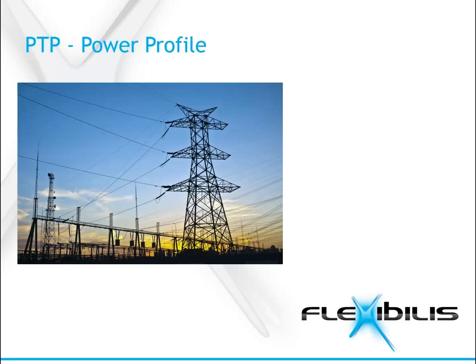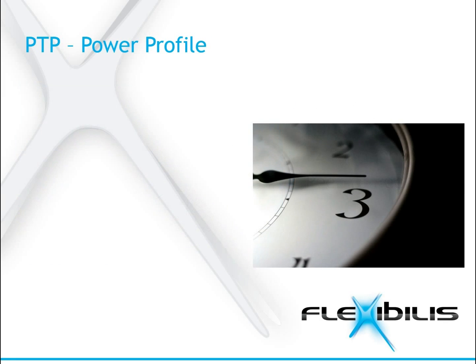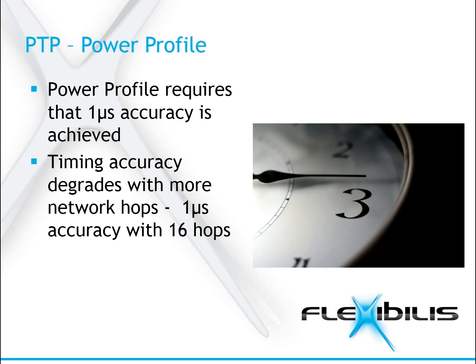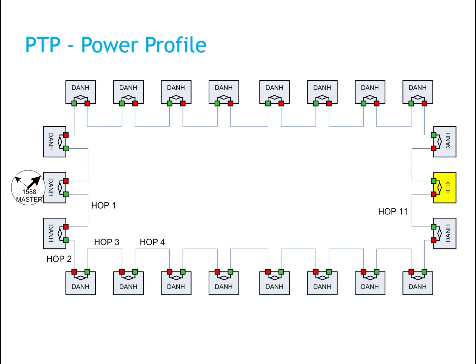The power profile is meant to be used in power system applications. It transfers PTP messages directly over layer 2 Ethernet and uses peer-to-peer transparent clock. The power profile requires that one microsecond accuracy is achieved. Timing accuracy degrades when the amount of network hops increases. The power profile defines the maximum number of hops from the Grandmaster to be 16. Here you can see an example picture with 11 hops between the master clock and an IED — intelligent electronic device — used in substation automation.